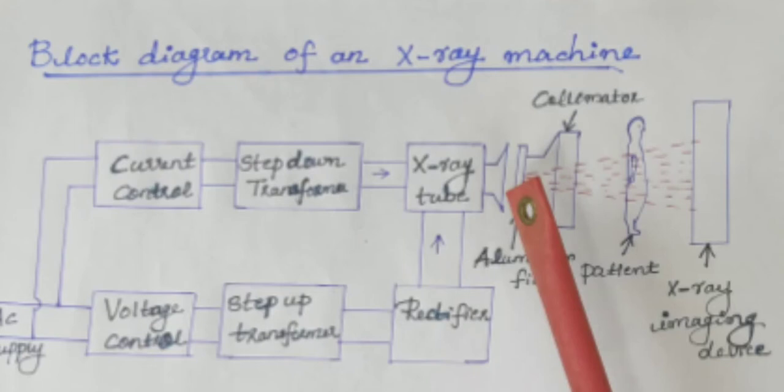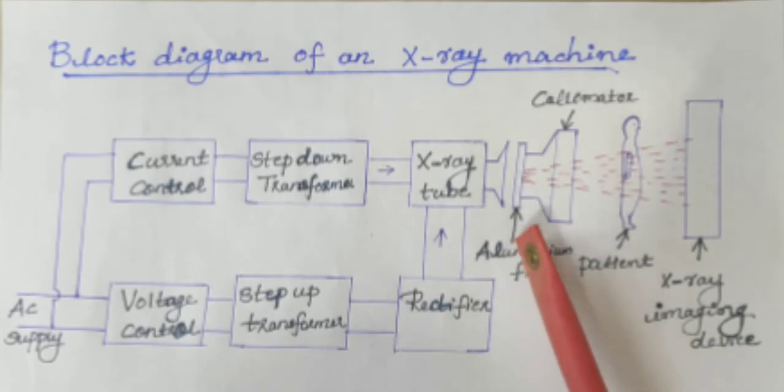Next one is the aluminum filter. Aluminum filters are used to attenuate or block low energy rays during x-ray imaging. Because low energy x-rays decrease the image contrast and they are heavily absorbed by the patient's soft tissue.